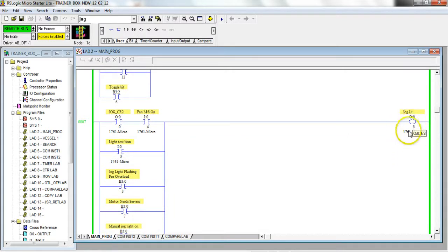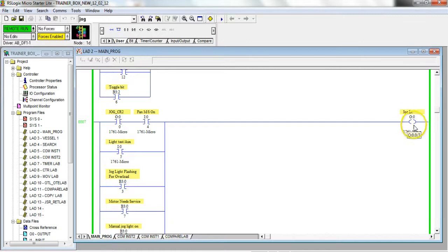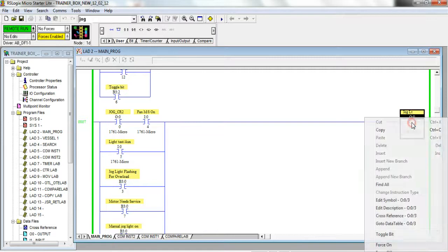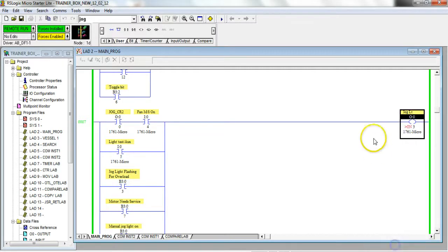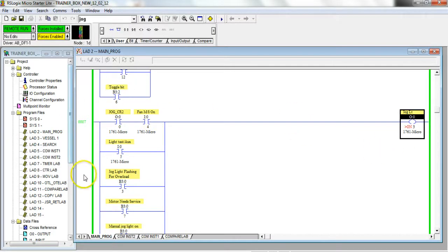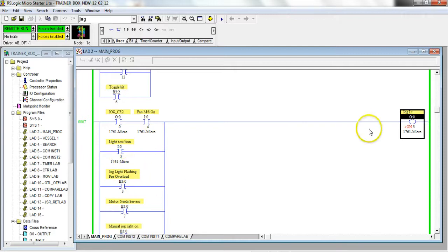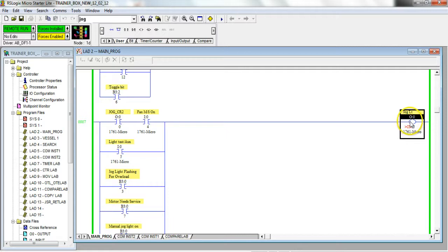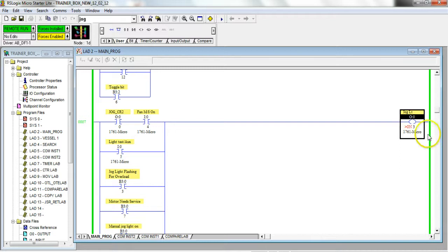Now that's forcing outputs. This jog light right here - if I wanted to test out this jog light and this is a light bulb, it's not a motor - you could, I say this about a light bulb now, you could safely force this on. That would be better than toggling it actually, because now you're not changing it everywhere in the program, you're just changing it and turning the light on.